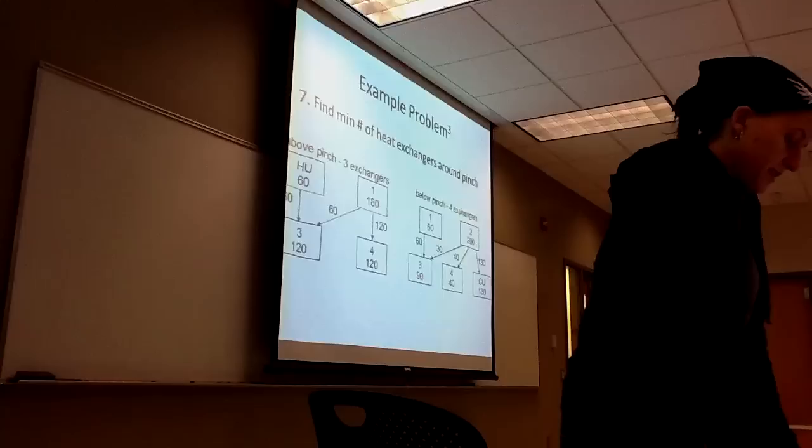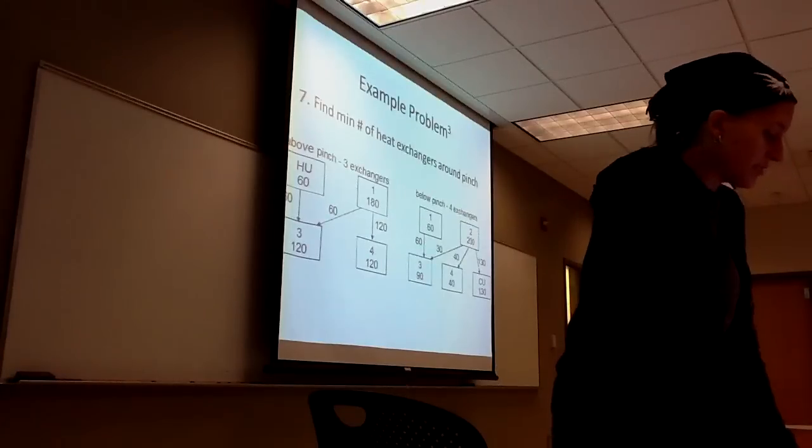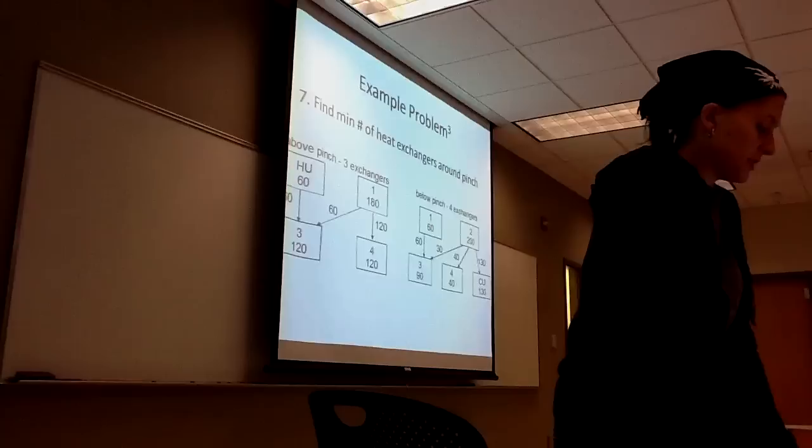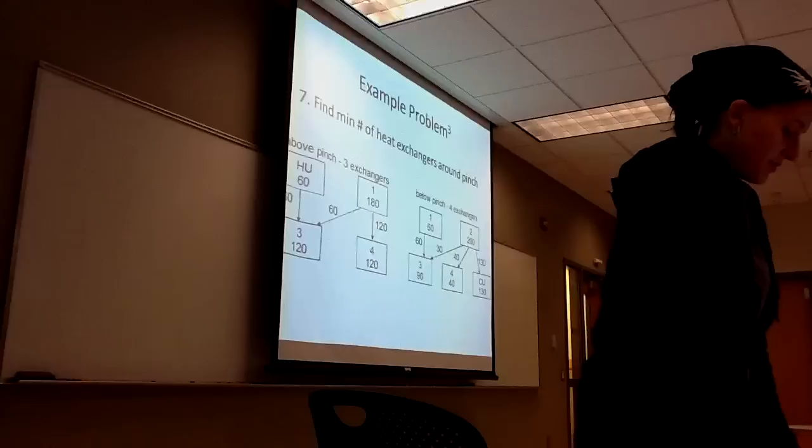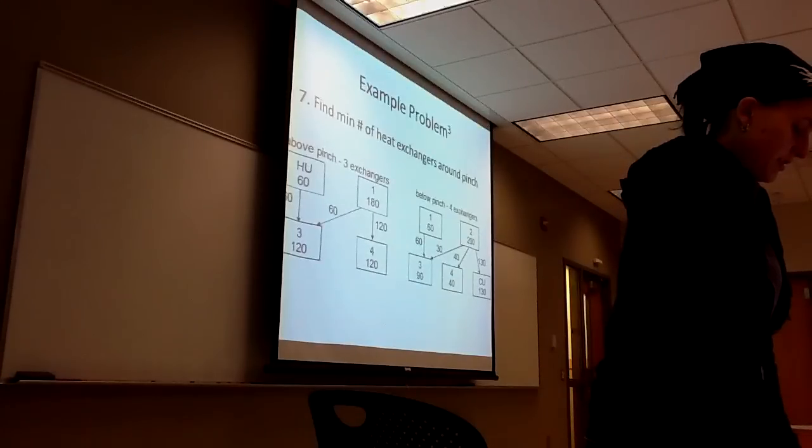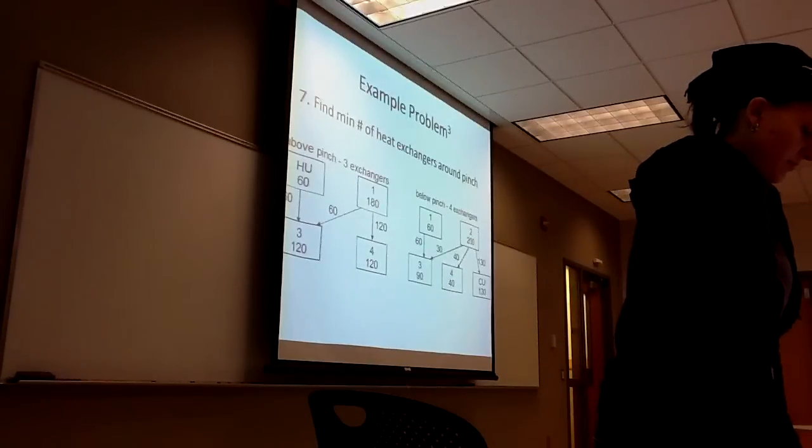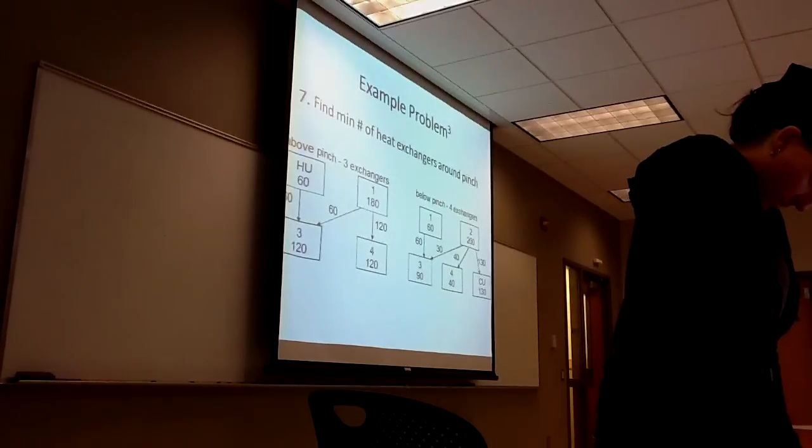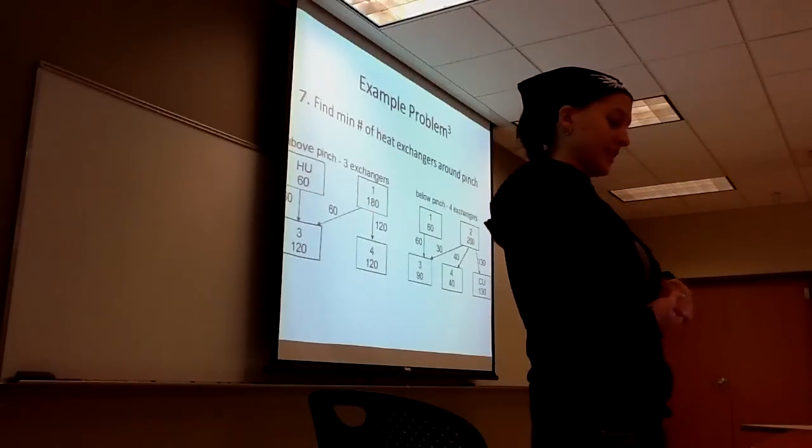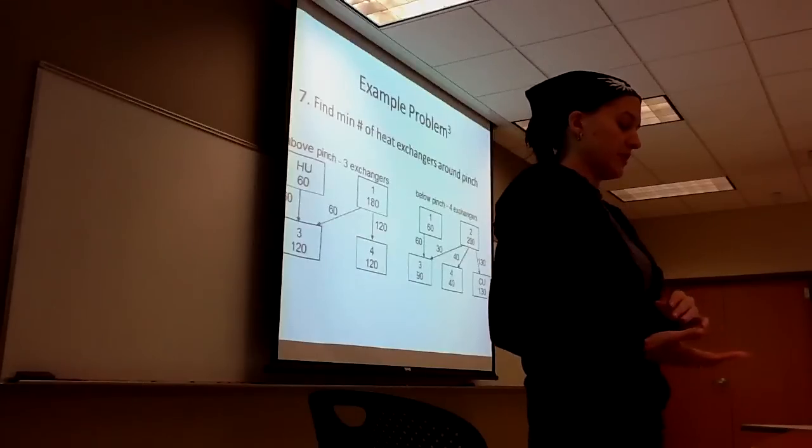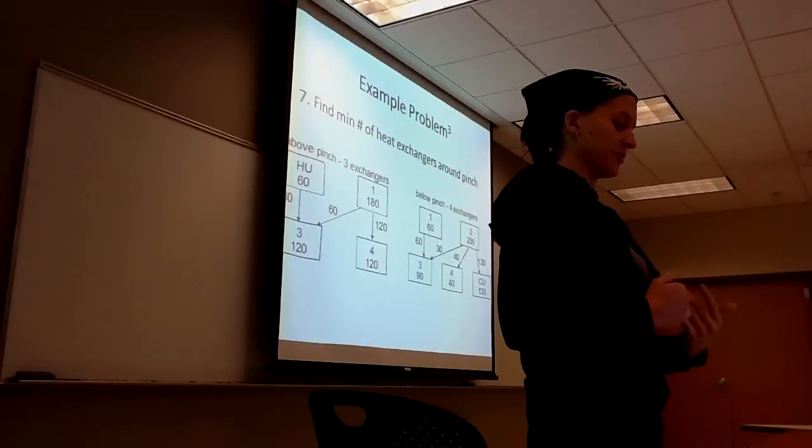This is representing the heat available in each stream, and available from the utilities above and below the pinch. The minimum number of heat exchangers is determined. The correct number of heat exchangers is the number of process streams plus the number of utility streams minus one.